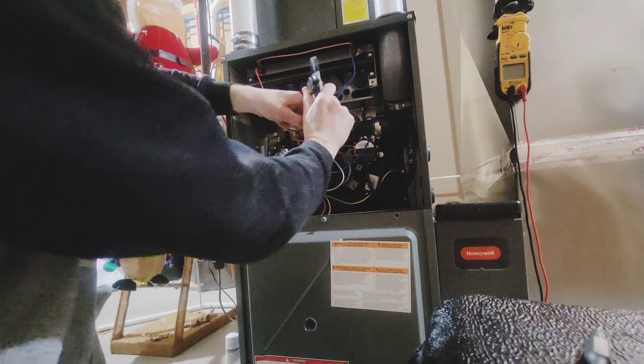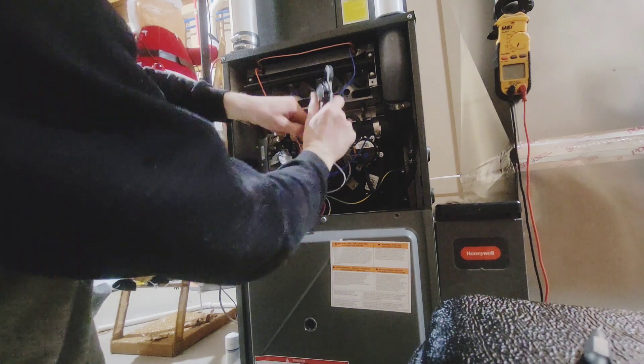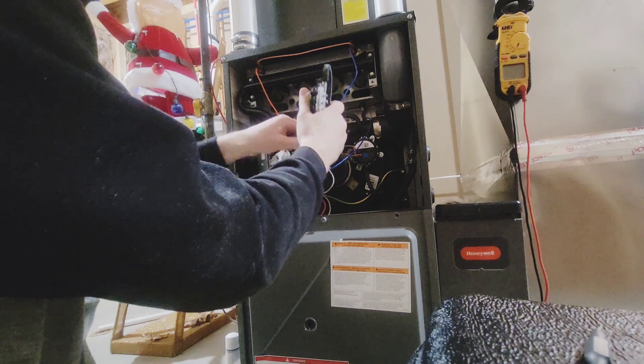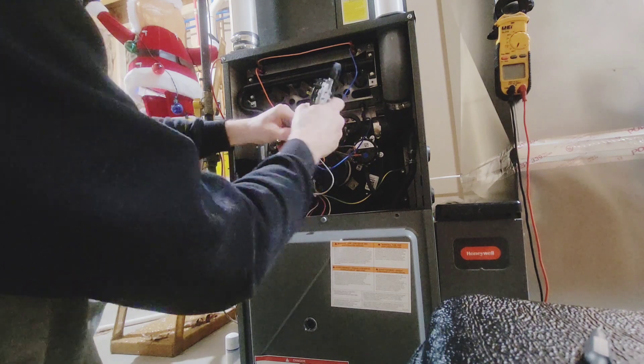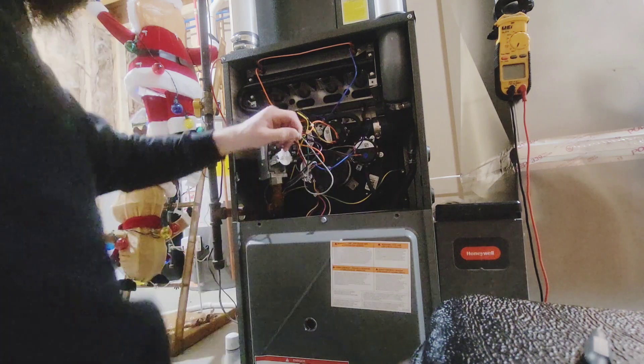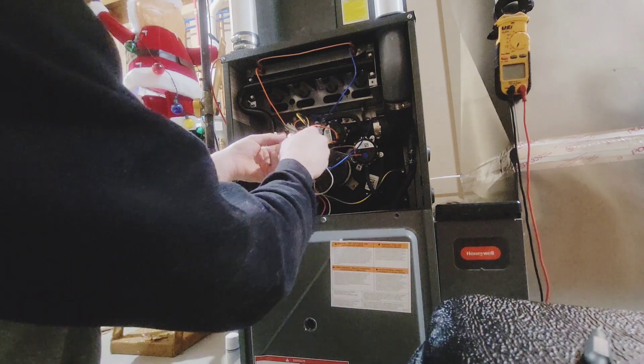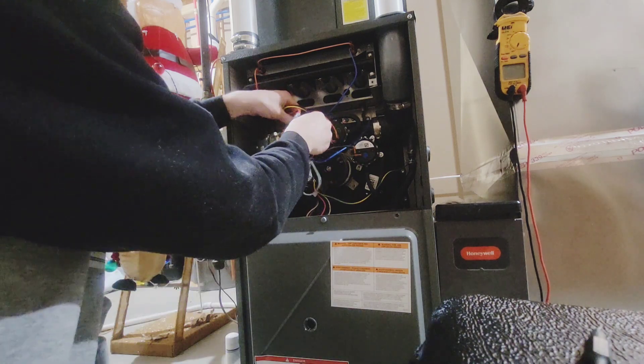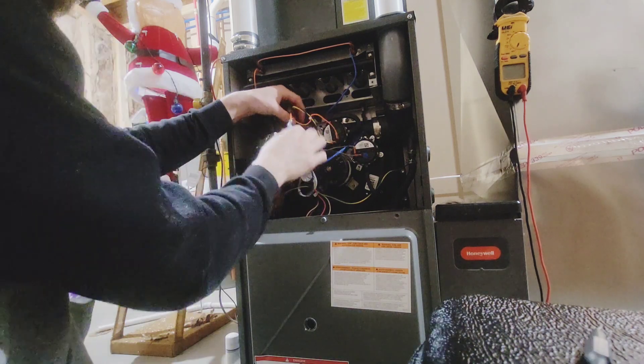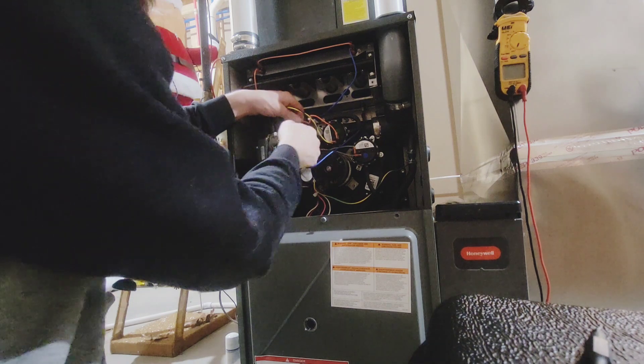This is very important that these wires go on that side. If it tries to start up in low fire or high fire, if your switches are reversed, which will say low fire and your high pressure switch isn't making because your wires are swapped, it's going to kill that furnace or not let it start up at all.